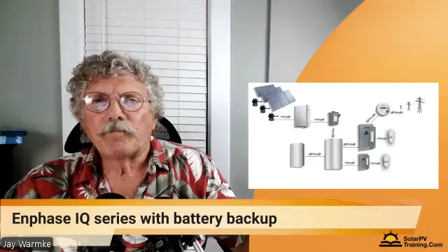But when we get into the microinverter world with Enphase, for example, here you've got AC generating inverters, microinverters on each panel. It then goes into a combiner box. The combiner box goes to an AC disconnect, which is typically out there next to your meter. And then it's going to connect into your smart switch, your auto transformer. That is what's going to then be the brains of the operation. From the auto transformer, you'll connect into a battery bank. The battery bank there is on the far left, the bottom corner.